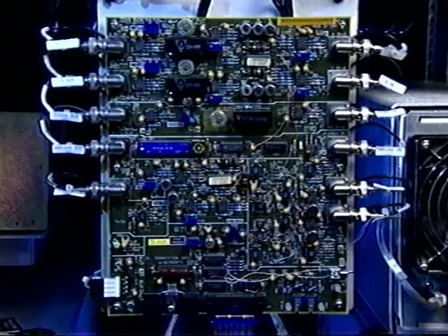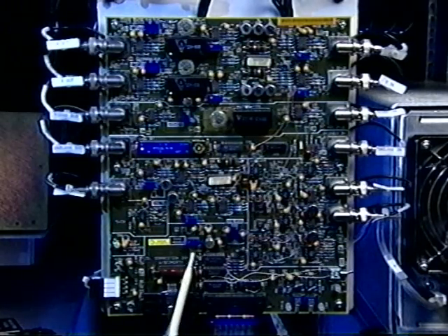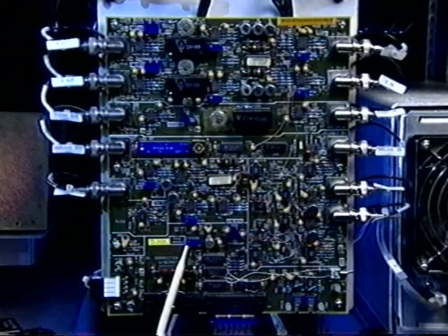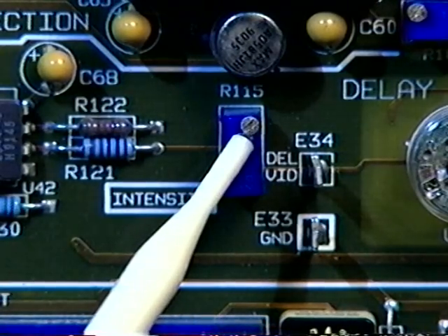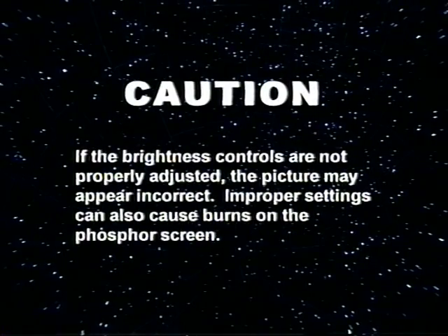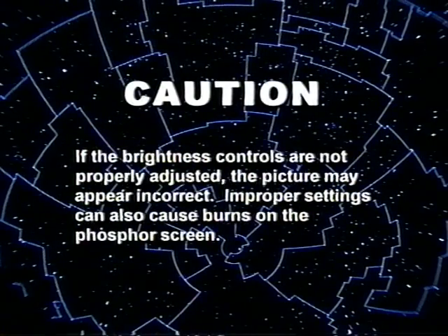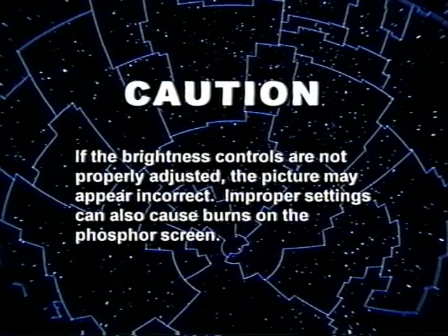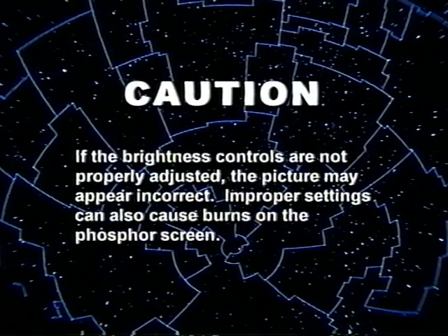Once the burn-in procedure is complete, the brightness controls must be set up before we can safely display an image. Brightness is determined by the proper adjustment of threshold, G2, and intensity controls on the correction card. Caution, if the brightness controls are not properly adjusted, the picture may appear incorrect. Improper settings can also cause burns on the phosphor screen. Note that phosphor screen burns are not warranted by E&S.